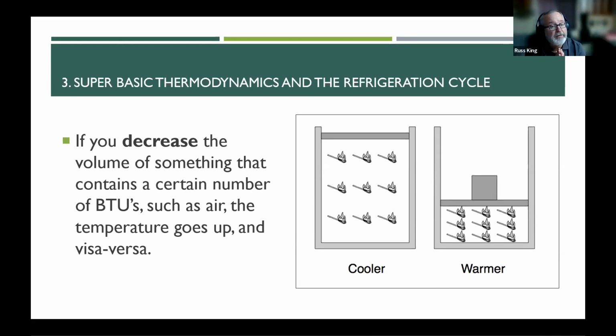That's a very interesting concept. And I don't know if anybody scuba dives or anything like that. You've ever heard about scuba tanks? When they fill a scuba tank with air, that tank gets really, really hot because they're taking all this air that has BTUs in it and they're compressing it into a smaller space. Another example, I don't have one here, but the little air cans that you spray to get the dust out of your computer keyboard. As that volume expands, the BTUs are getting farther apart, they're getting less dense, and it cools off. Okay, that's the principle that we're talking about.